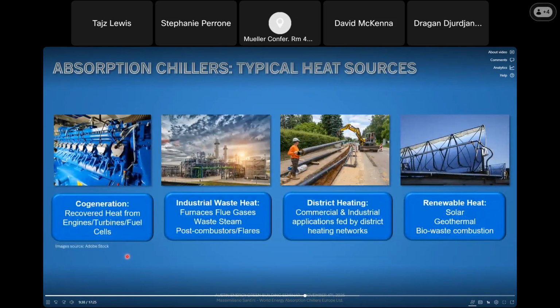This slide illustrates the most typical heat sources for absorption chillers. Cogeneration with heat recovered from engines, turbines, and fuel cells. Industrial waste heat, such as furnaces, flue gases, or post-combustors. District heating networks, very used, especially in commercial or institutional buildings, or renewable heat with solar thermal, geothermal, or bio-waste combustion.